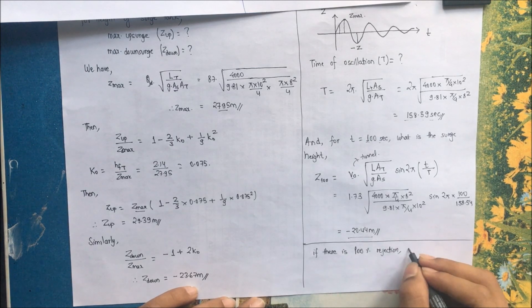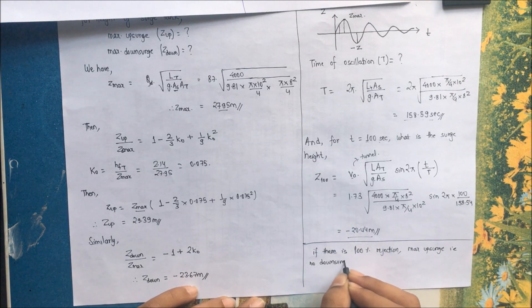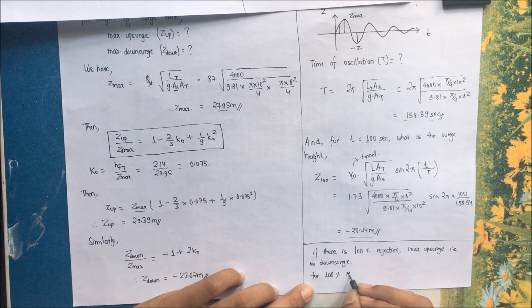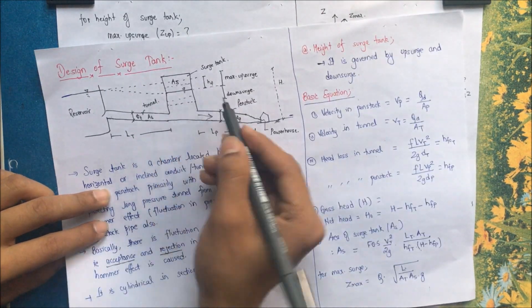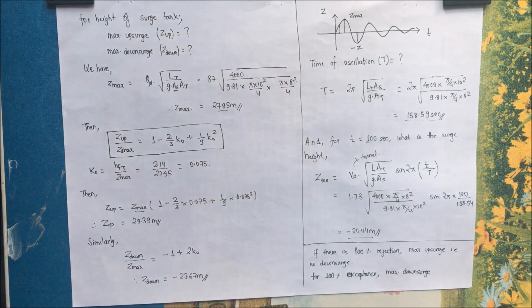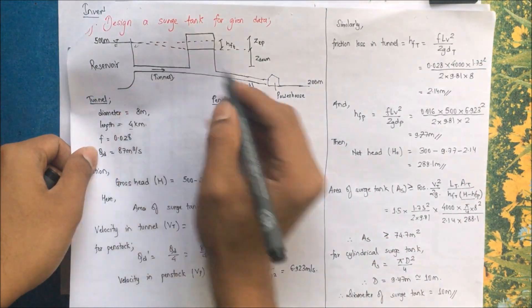Note: if there is 100% load rejection, there will be maximum upsurge and no downsurge. For 100% load acceptance, there will be maximum downsurge — the water level in the surge tank drops to its lowest. Invert level is the base interior level of a pipe, trench, or tunnel — considered as the floor level — and is an important datum for determining the flow line of a piping system.